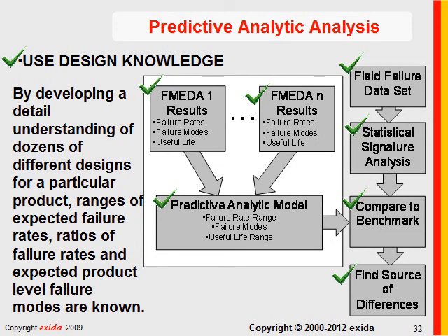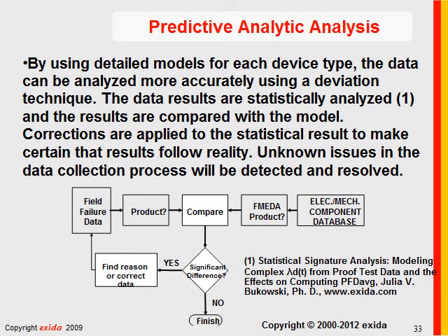So I think the predictive analytic models are just very valuable for checking integrity and developing confidence in field failure data. We often do comparisons between the data set and the FMEDA on a product basis, and any differences, we find the reason. I did provide you a reference on statistical signature analysis, a method developed by Dr. Julia Bukowski while working for exida.